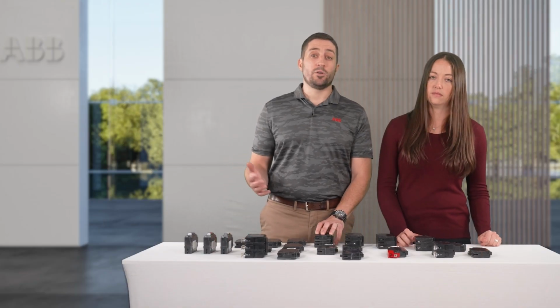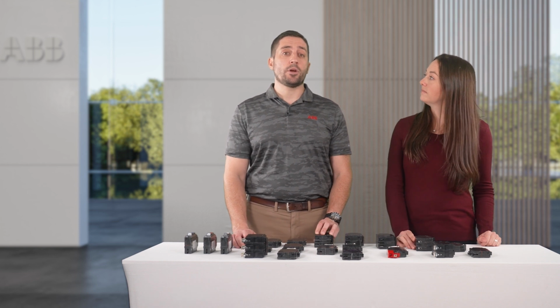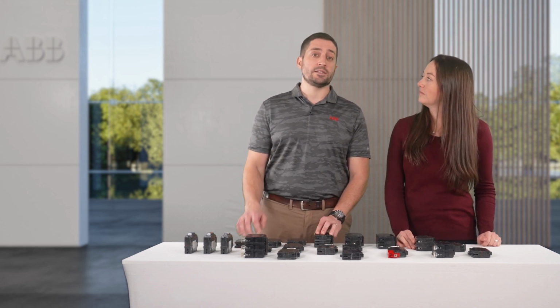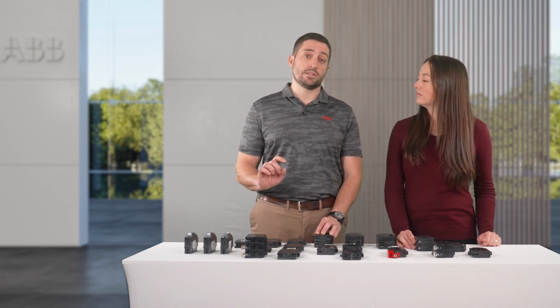The National Electric Code, or NEC, recognizes that the operation of overcurrent protective devices may be affected by the heat within a system. Because of this, it defines the concept of continuous loads and the 80% limitation in order to try and offset the effects of heat in the system when sizing a circuit breaker. If we have to size a circuit breaker rating to 125% of the continuous load current, then we are only utilizing 80% of the circuit breaker's current carrying capacity.